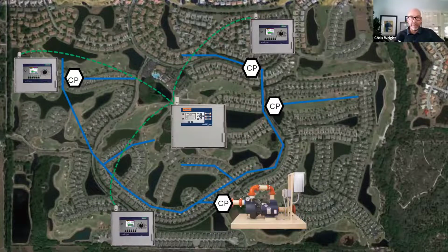So the takeaway and the thing to remember is the functionality, as we call it in baseline language, is control point grouping. And what that means is if we've got a single 3200 on this hydraulic structure and control point 2, which is a leg off of the mainline, calls for water, the 3200 needs to know to turn on the pump station and also to open that control point. So it's opening 2 different control points, right? In order to provide water for that leg. That's how that functionality works. And it's called control point grouping.